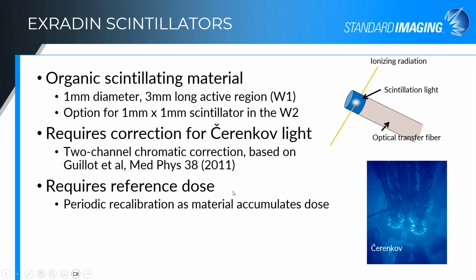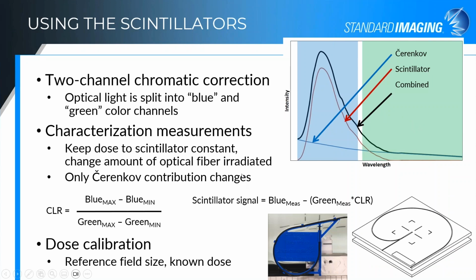It's about a 2% per 1,000 gray decrease in signal. But if you recalibrate at that point, you have a slightly lower signal, but you can continue using the device for quite some time. This 2-channel chromatic correction that we use is essentially splitting the light into what we're calling the blue portion of the spectrum and the green portion of the spectrum.